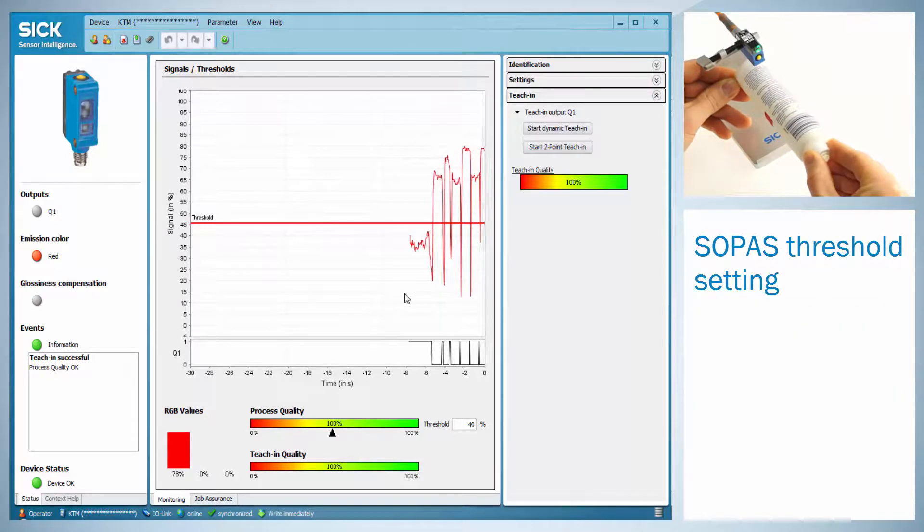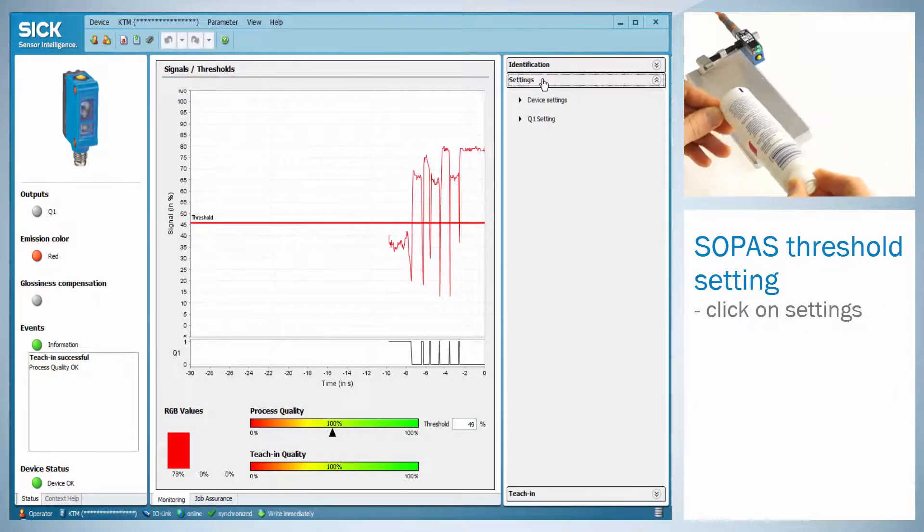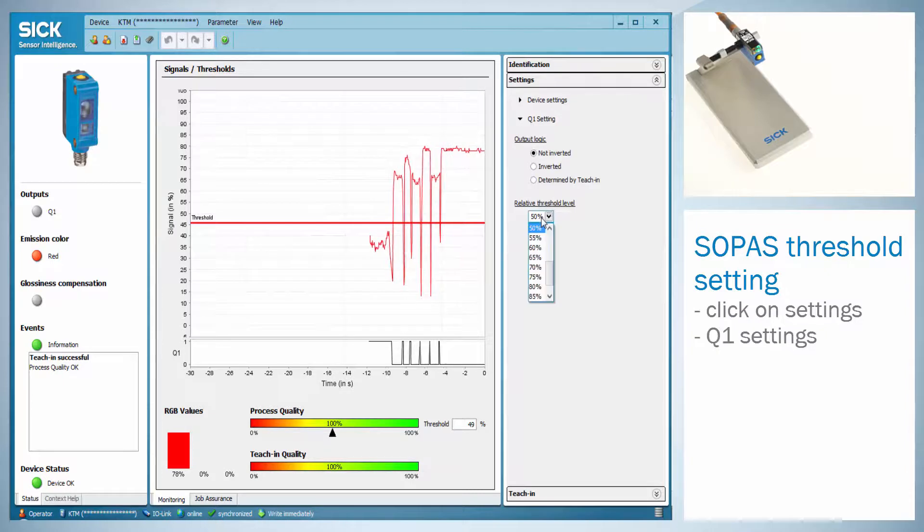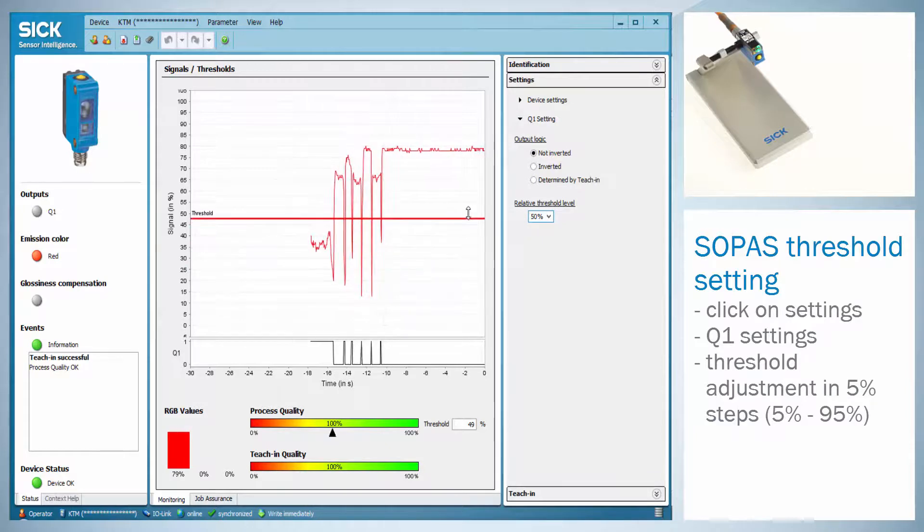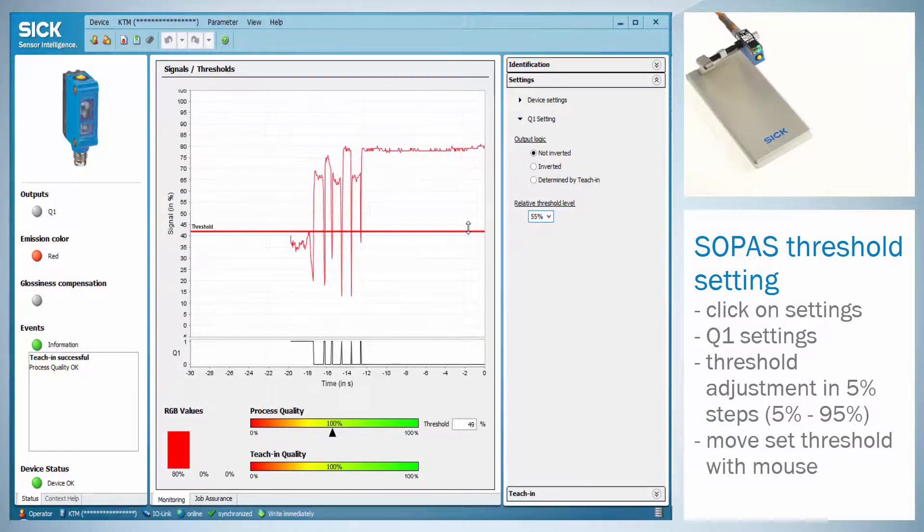The threshold of the switching output can be adjusted by clicking on the settings flag and then on Q1 settings. The threshold can be adjusted in 5% steps between 5 and 95%. Another way is moving the threshold level with a mouse on the central screen.